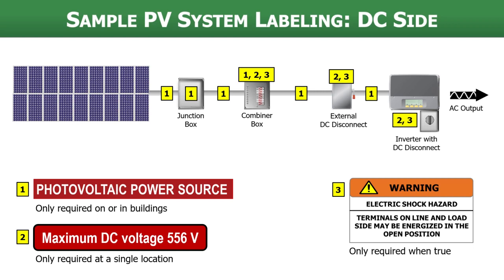So here we have the label placed on the external DC disconnect or at the inverter with an integral DC disconnect. Again, you might have to talk to the inverter manufacturer and ask about the capacitors on the DC side. How long do they remain energized and discharge voltage that would make the load side of a disconnect live?